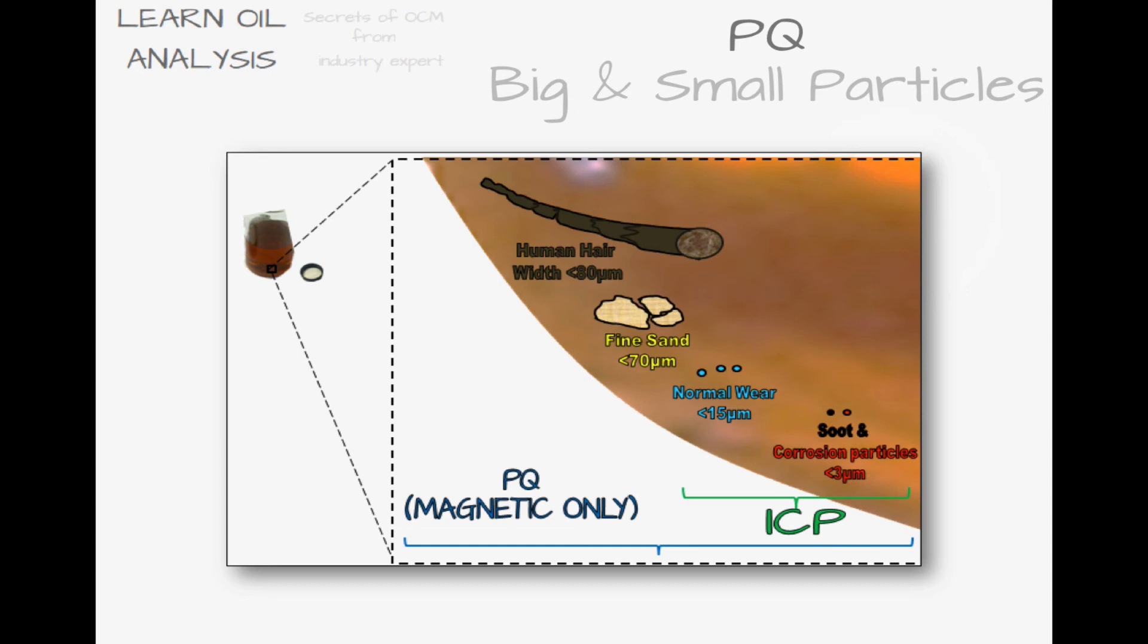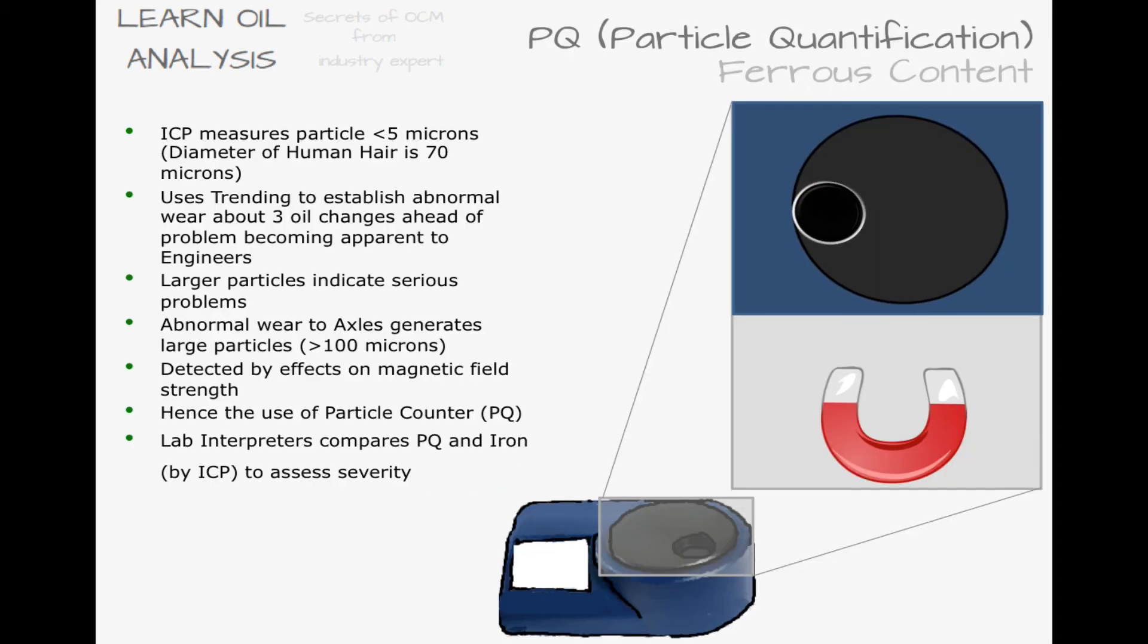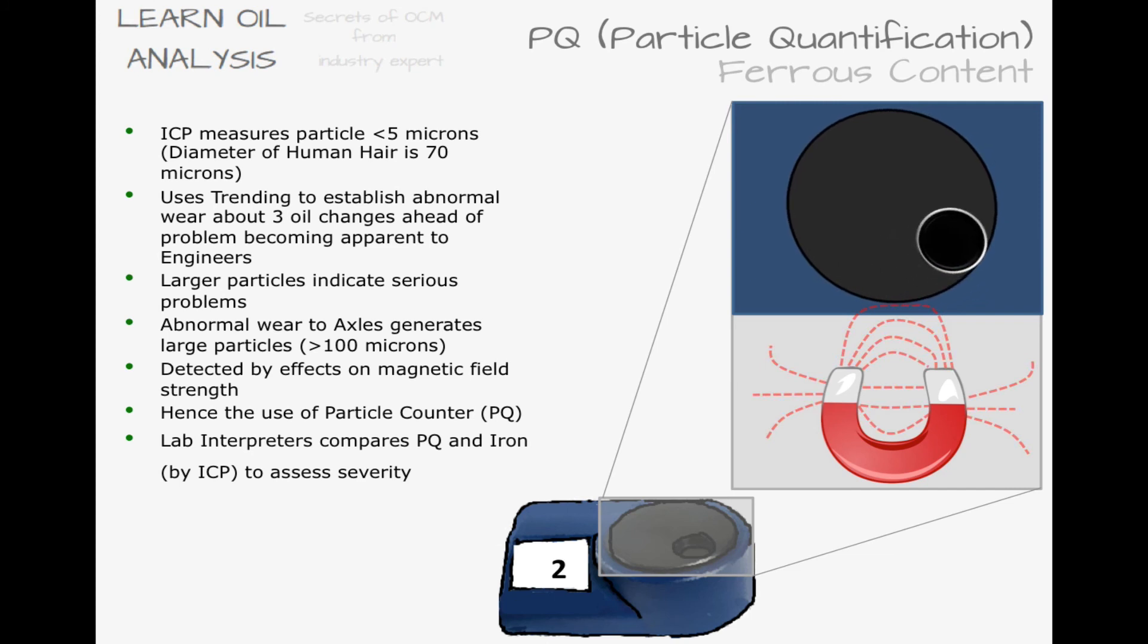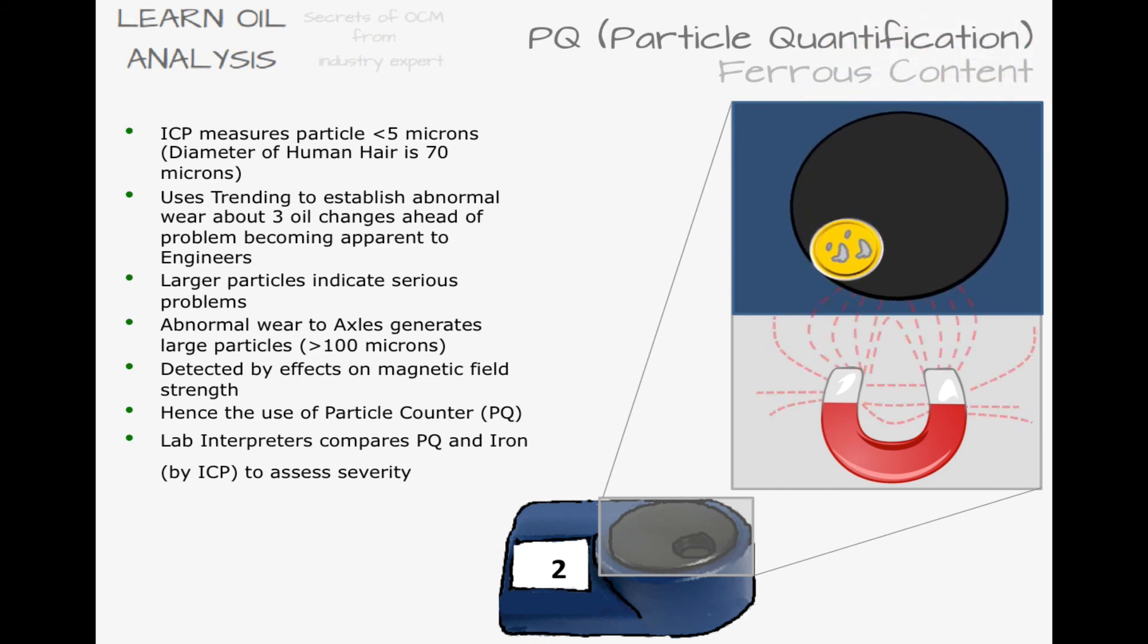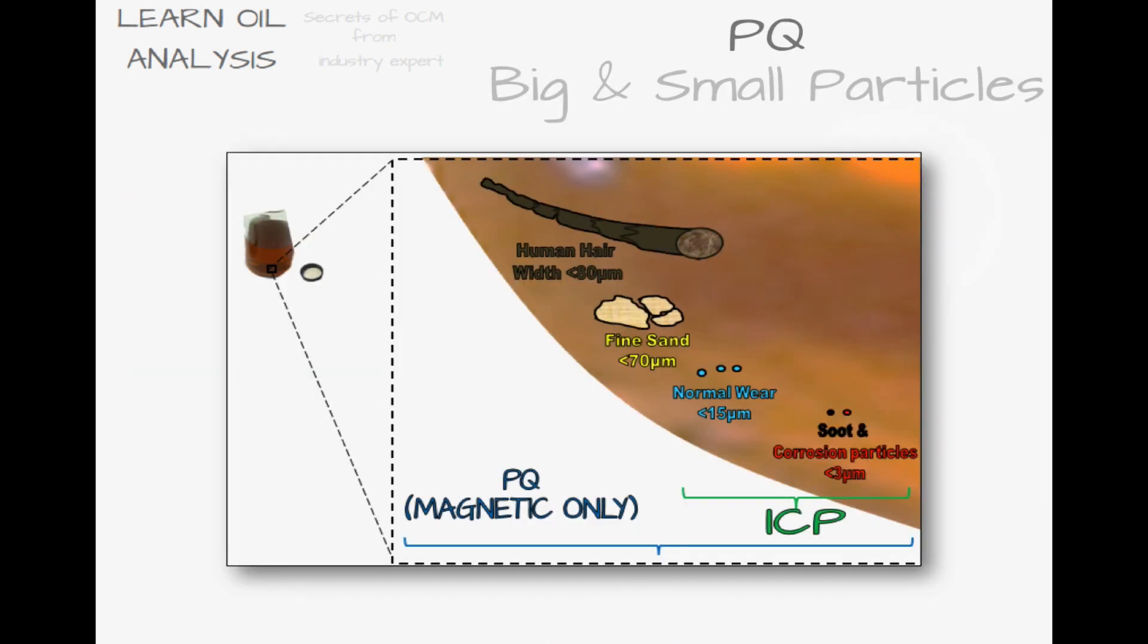PQ on the other hand is a unitless measure of ferrous particles in the sample. The test works by sample cup or bottle rotating through a magnetic field and the disruption to the magnetic field is measured. In the first spin we can see there is very little disruption to the magnetic field and this could be simply background magnetism to give a reading above zero. When we add a sample with a very high ferrous content it causes a high PQ reading as it disrupts the field. PQ does not only measure small particles but large particles too so it is an excellent complement to ICP to measure small and big particles.